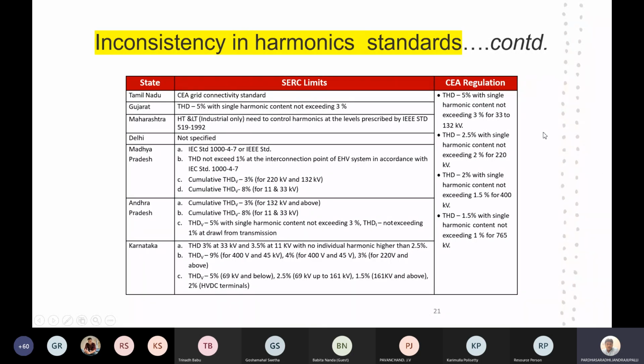According to CEA, THD of 5% with single harmonic content not exceeding 3% for 33 to 132 kV is accepted, whereas THD of 2.5% with single harmonic content not exceeding 2% for 220 kV, for 400 kV 2% with single harmonic content not exceeding 1.5%, and THD of 1.5% with single harmonic content not exceeding 1% for 765 kV. These are from the Central Electricity Authority. They said these are the different standards according to the Indian voltage regulations. So these are the IEEE as well as Indian standards.